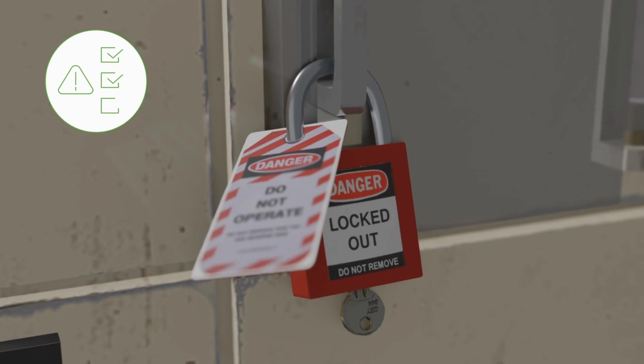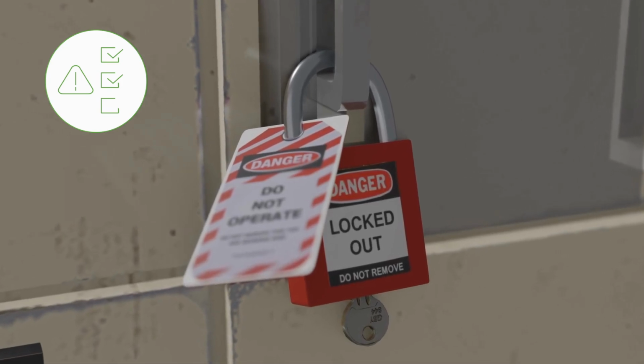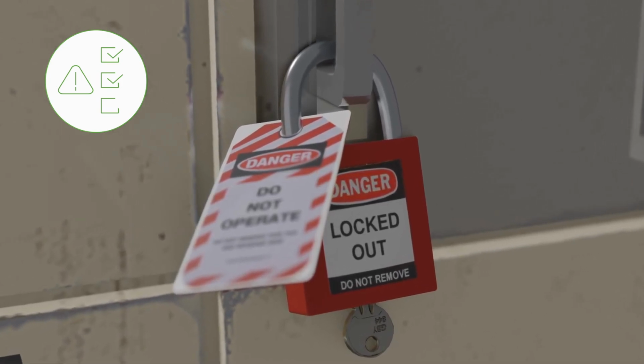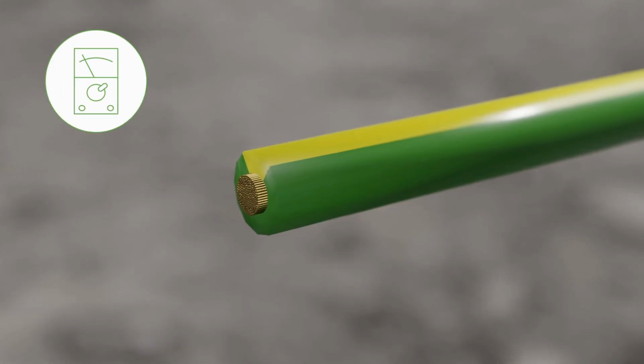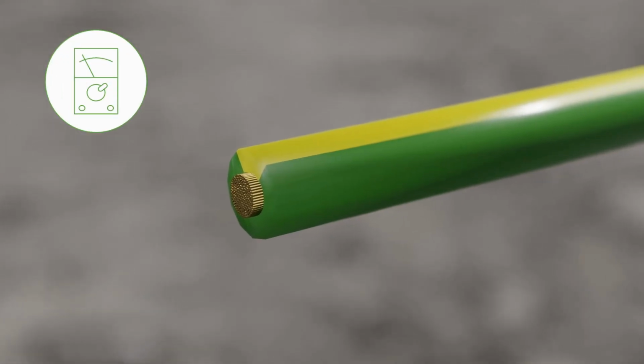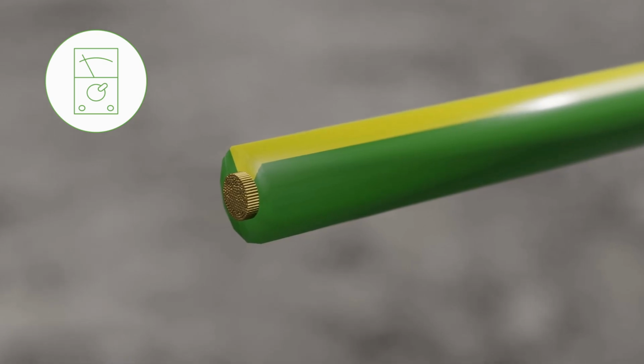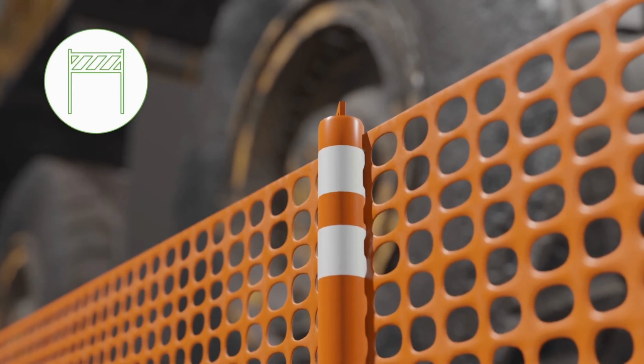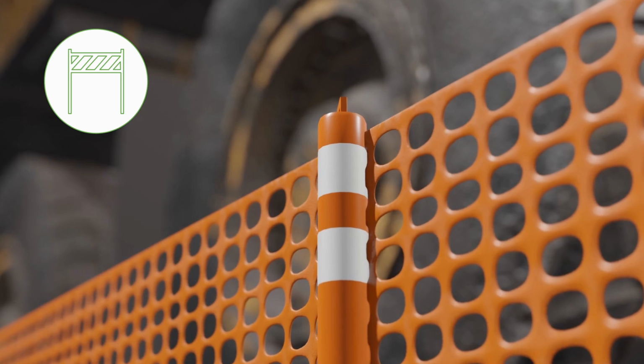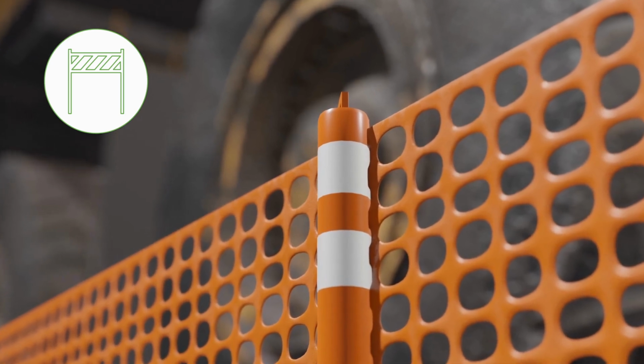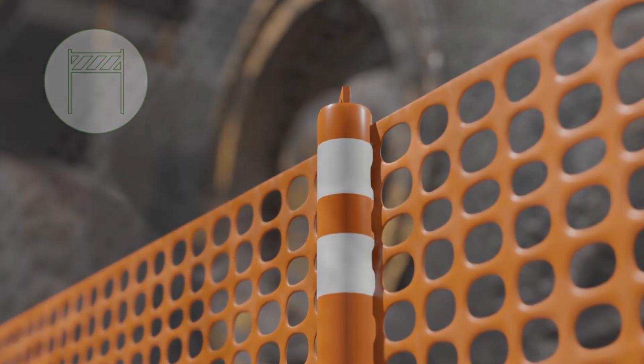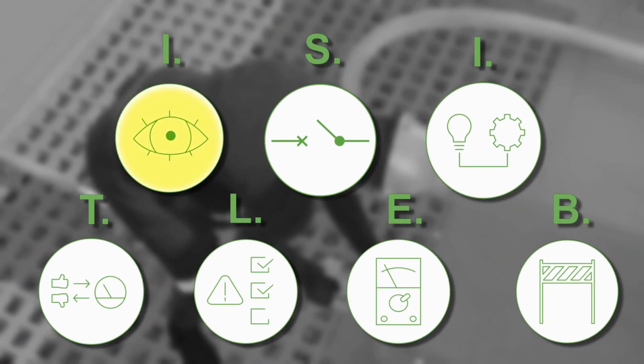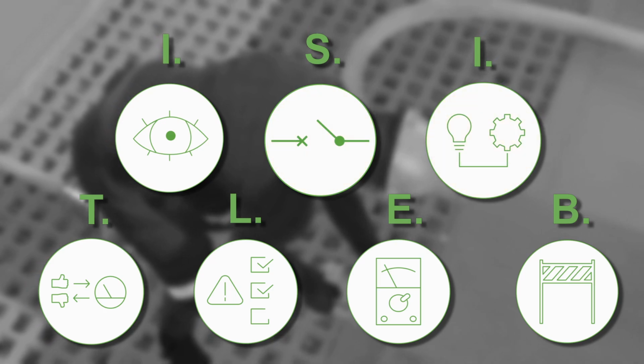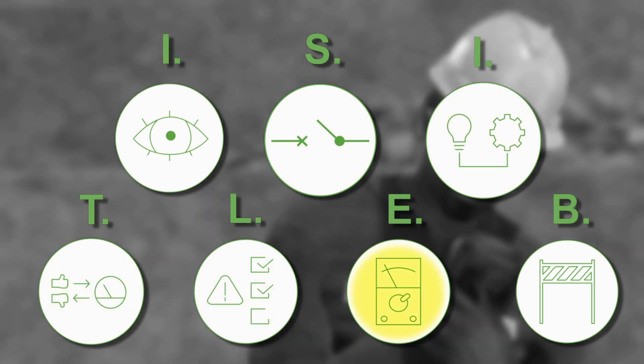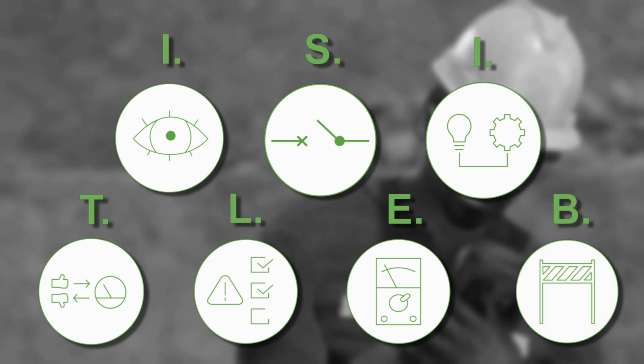Lockout: secure all isolation points with locks and tags to prevent re-energization during maintenance. Earth: safely discharge stored energy and apply earthing to eliminate residual risks. Barricade: clearly mark hazardous areas and set up barriers to protect the team and others from potential dangers. By rigorously following the I-SIT-LEB process, each step keeps safety as a priority and addresses hidden dangers. If this protocol had been followed, the arc flash could have been prevented.